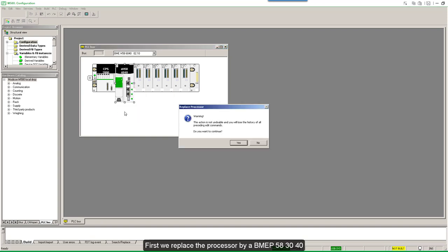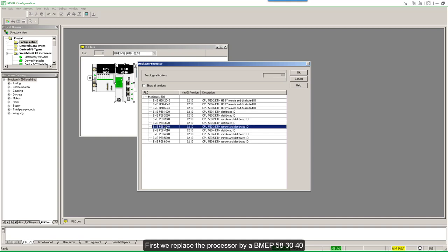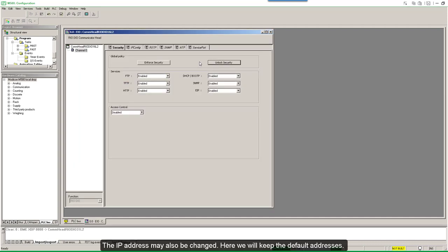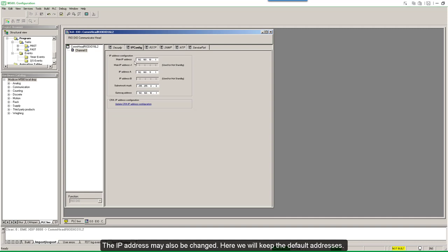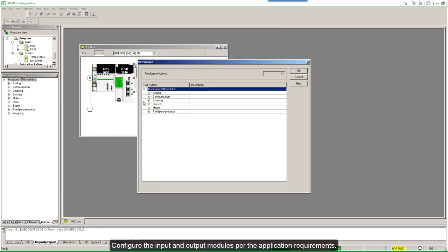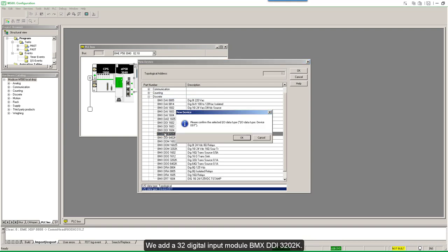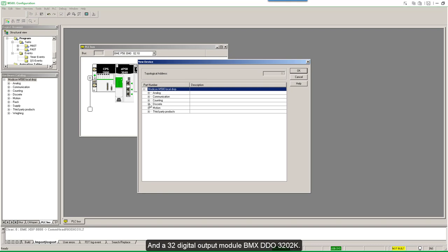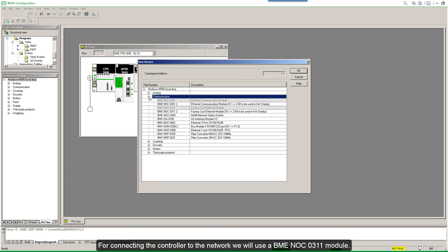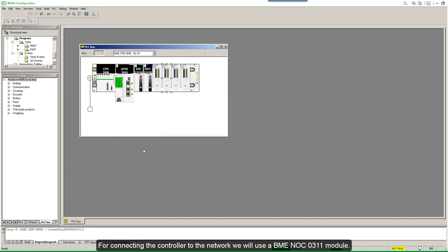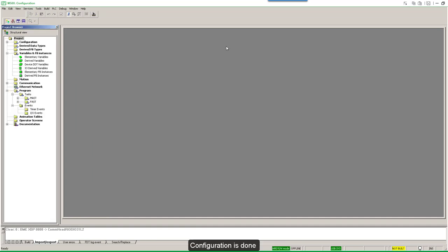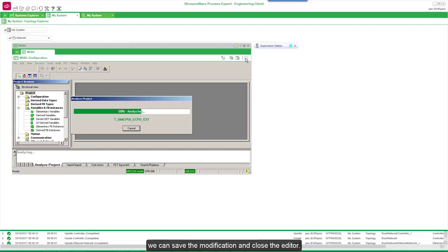Open the Configuration tool from the M580 context menu. The graphical configuration editor opens on a new M580 configuration. First we replace the processor with a BME P583040. Then modify the Ethernet security to enable the service as needed. The IP address may also be changed; here we will keep the default addresses. Close the window and accept the modifications. Configure the input and output modules per the application requirements. We add a 32 digital input module BMX-DDI3202K and a 32 digital output module BMX-DDO3202K. For connecting the controller to the network we will use a BME NOCO311 module. The IP address can be configured in the module; here we will keep the default address. Configuration is done; we save the modification and close the editor.